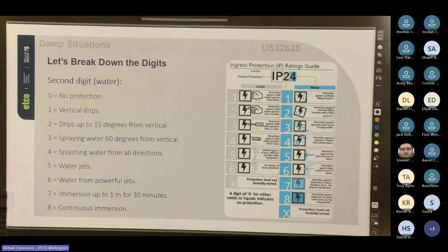So a socket marked IP20 is finger safe, but it's useless against splashes. We compare that to IP67, which can survive full immersion in a meter of water. That's why we can't just throw in any fitting. The rating has to suit the location. So when we buy a light fitting and it's IP44, we think it's safe to stick in a damp area? Yes. But if that damp area is going to be subjected to washdown, we must have at least an IPX6, or I would go with an IP67, just to have that one level above water from powerful jets.